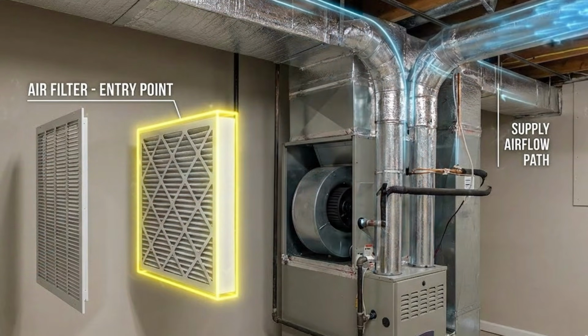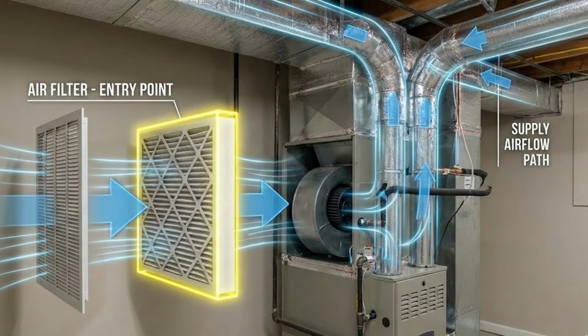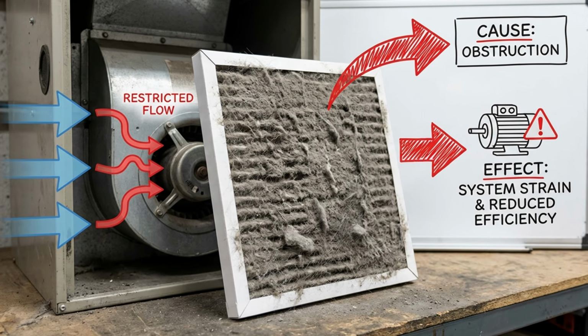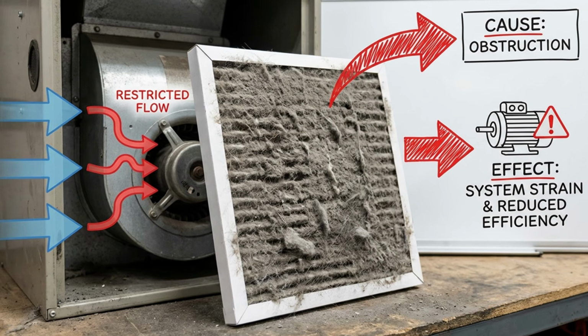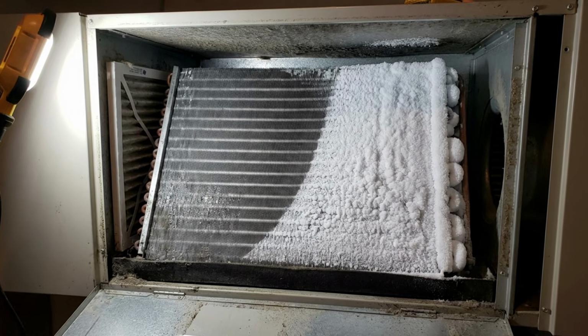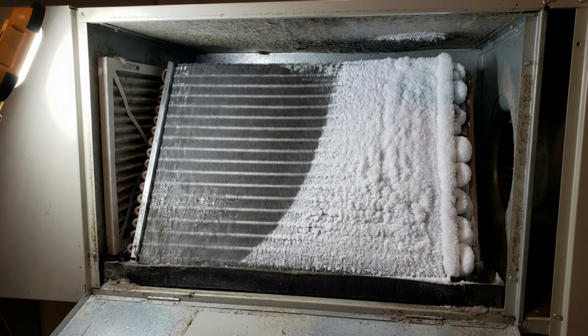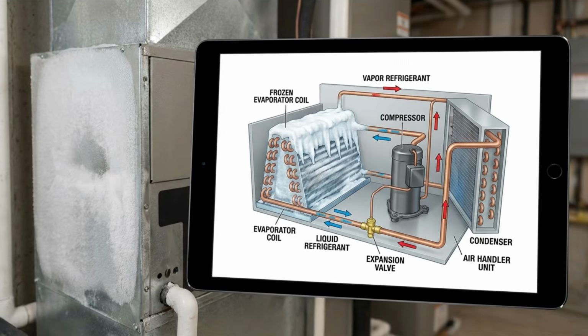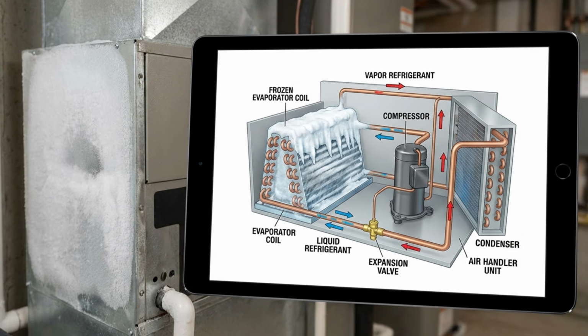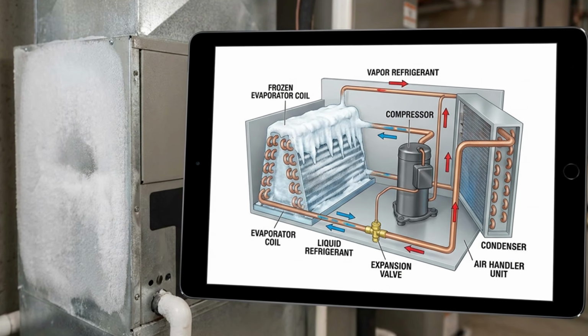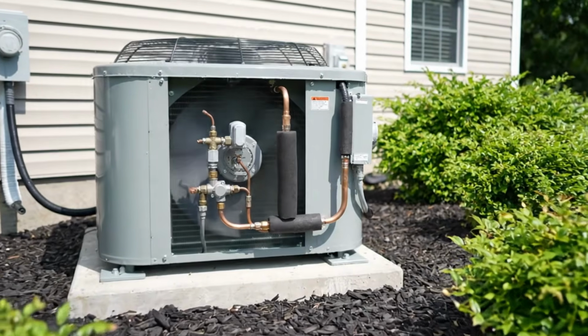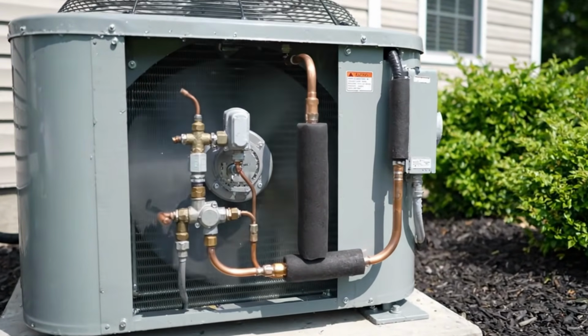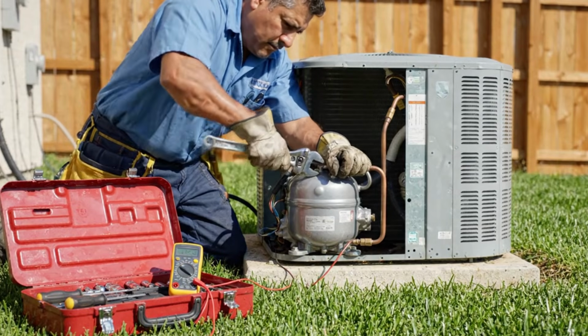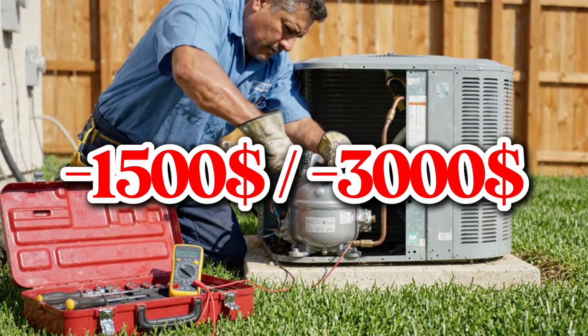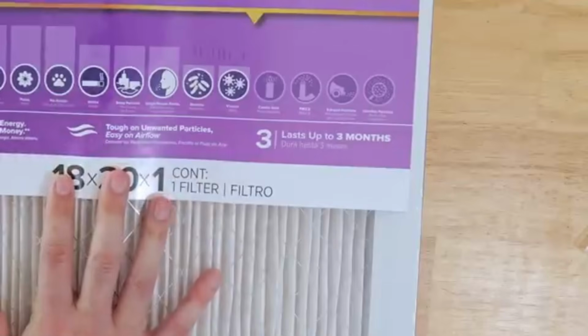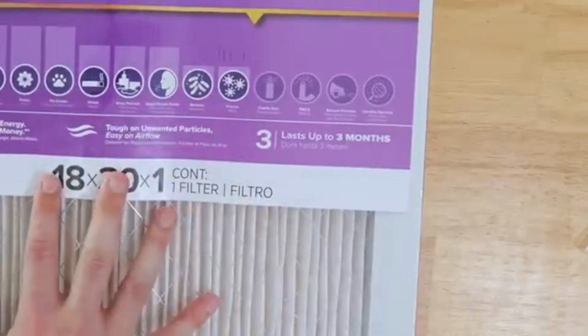When airflow is restricted, and a clogged filter restricts airflow, your system has to work harder to move the same amount of air. The blower motor strains. The evaporator coil runs colder than it should, sometimes cold enough to freeze. And a frozen coil doesn't just stop cooling your house, it can force liquid refrigerant back into the compressor, which is the single most expensive component in your system. A new compressor typically runs $1,500 to $3,000 installed. A filter costs $10 to $25.